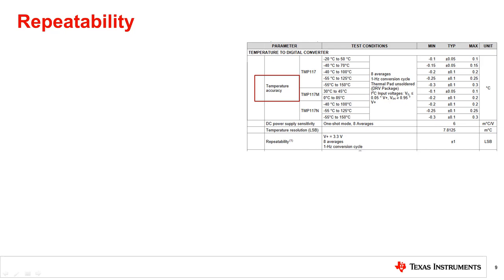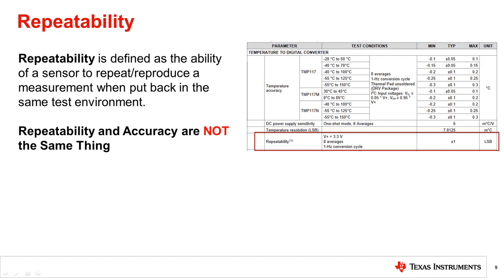Another important parameter to be considered when making highly accurate measurements is repeatability. Repeatability is defined as how consistent a sensor is against itself — it describes the ability of a sensor to provide the same result under the same circumstances over and over again. For instance, a temperature sensor with a repeatability of ±1 LSB, where the temperature resolution is 7.8125 m°C, means that measurements made under the same exact test conditions should be within 7.8125 m°C of the mean of those measurements.